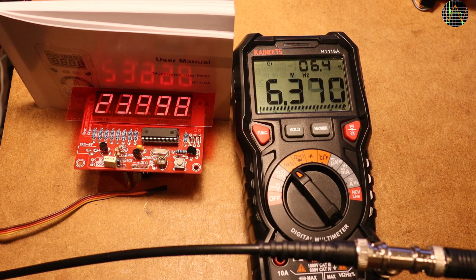It takes some minimum signal before that can be done. In this test, I increase the signal slowly until we get a stable frequency display. We get some movement at just about 62 mV, but the value is not correct yet. At 67 mV, we get a reasonable value. That's better than the BM869S, which still displays zeros until we reach just over 70 mV.